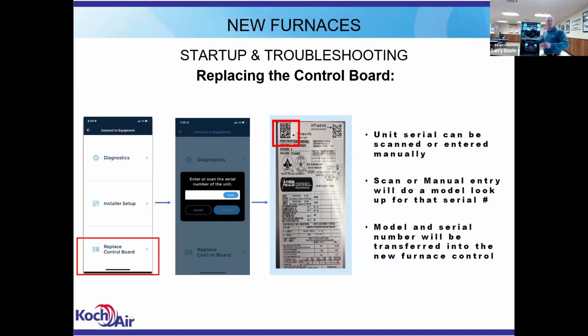You're just changing settings. When we're configuring a replacement board, we have to have either cell phone service or internet access to our app. And the reason is we're going to plug in that serial number and it's going to sync up with the database. And it's going to find that serial number and select the furnace model number and pull that information down and tell you, okay, the serial number you selected is this furnace. And here's the menu for it.